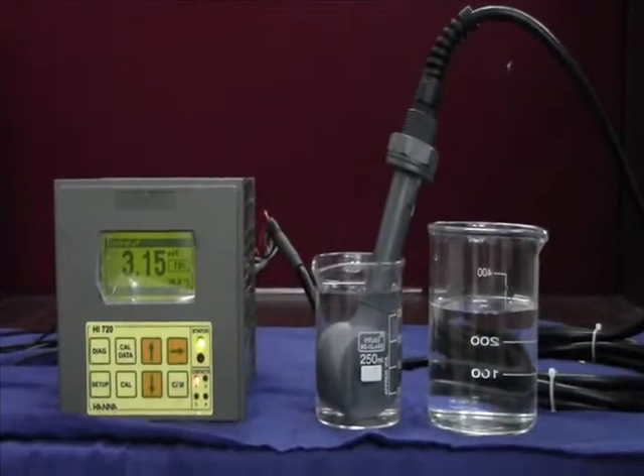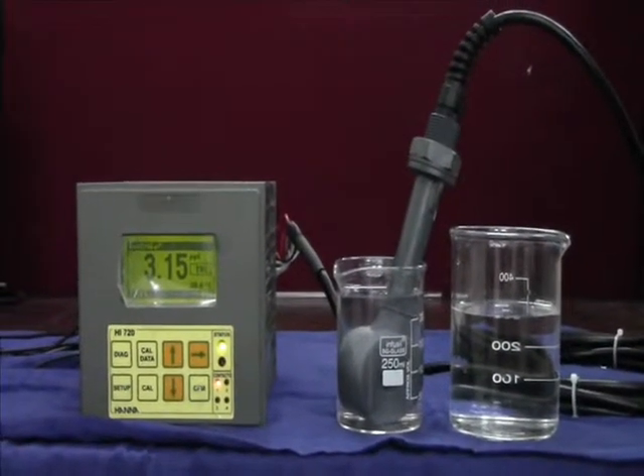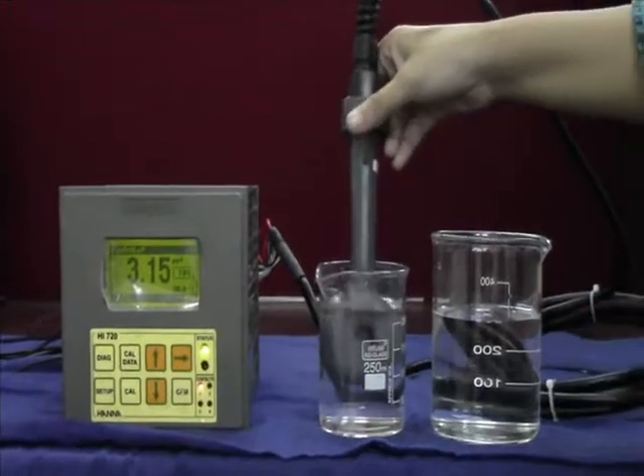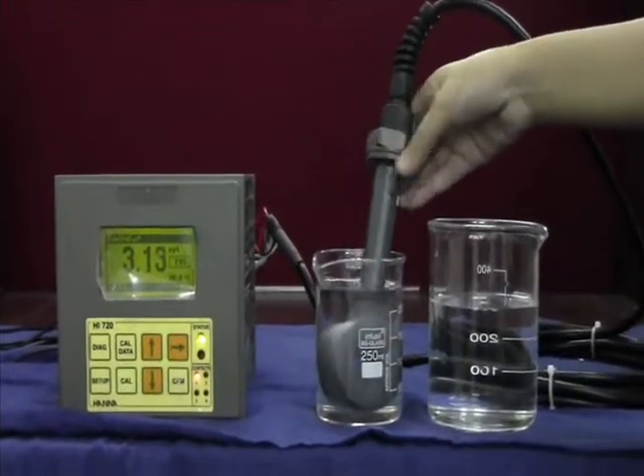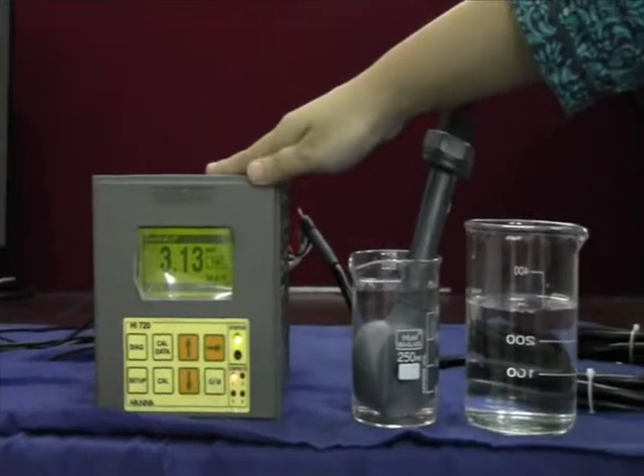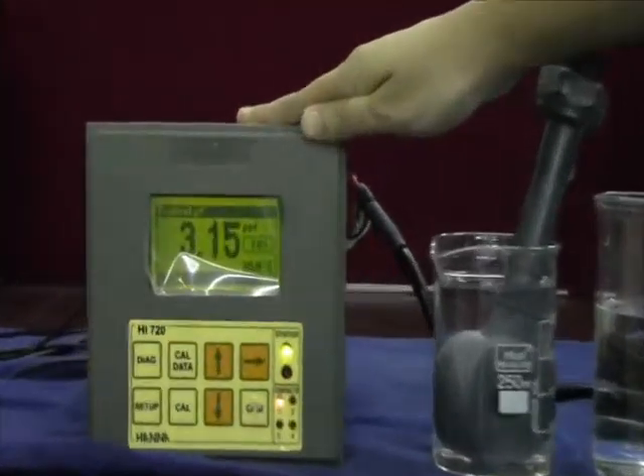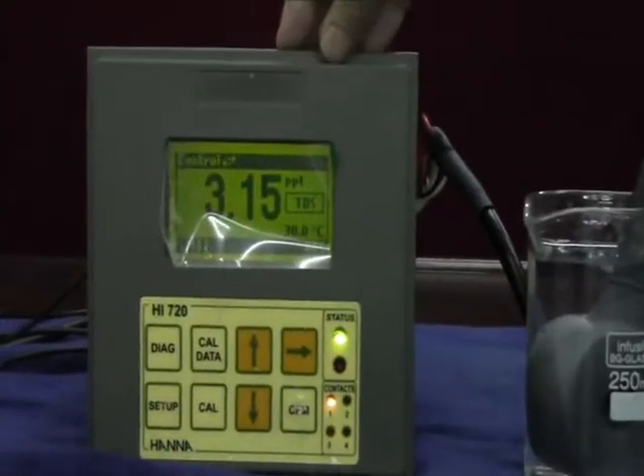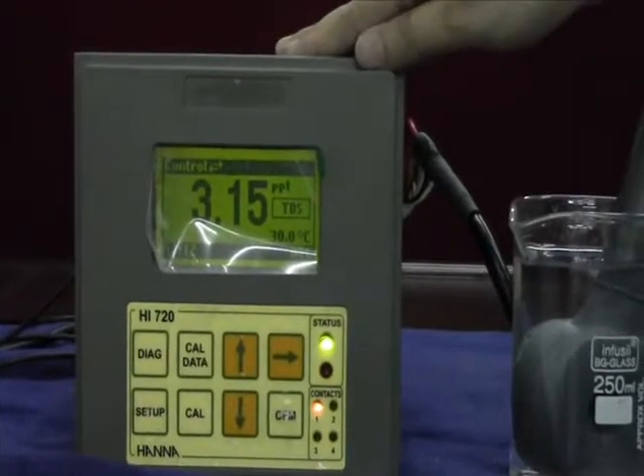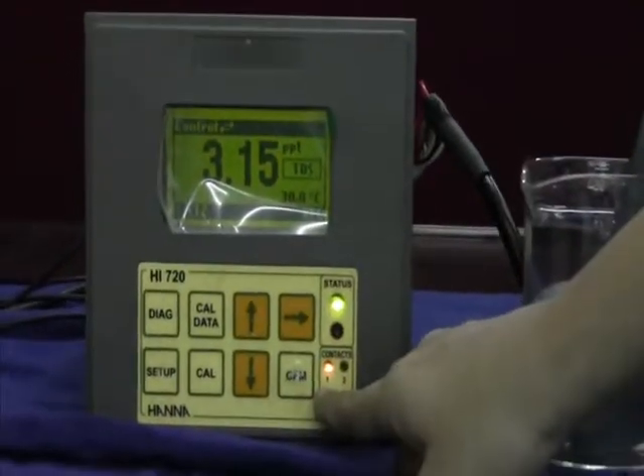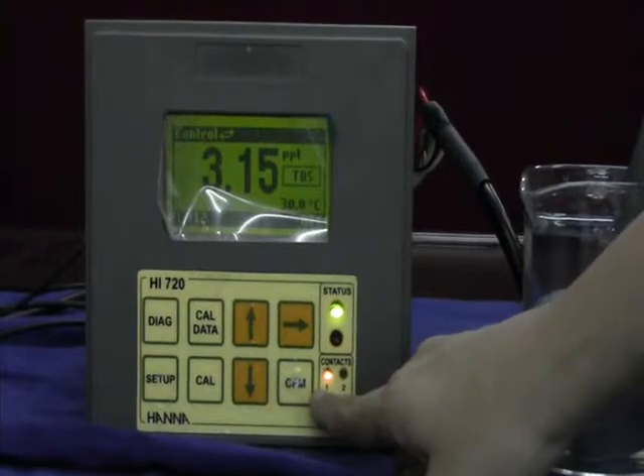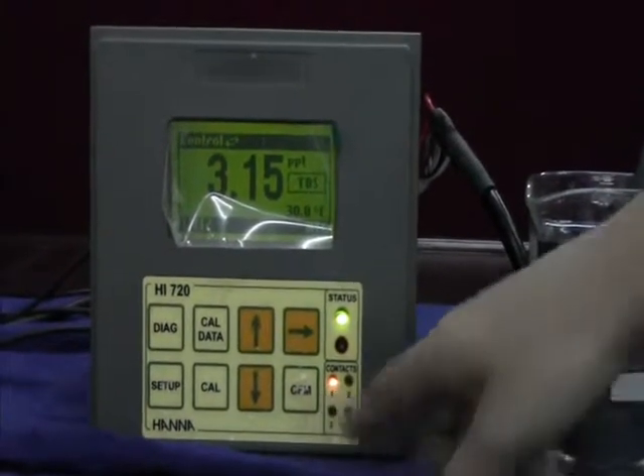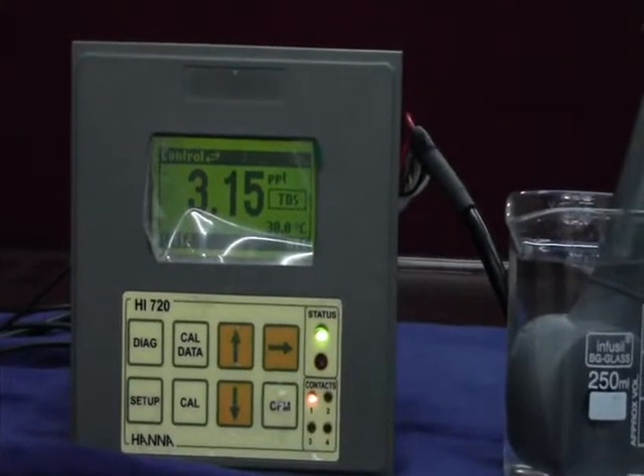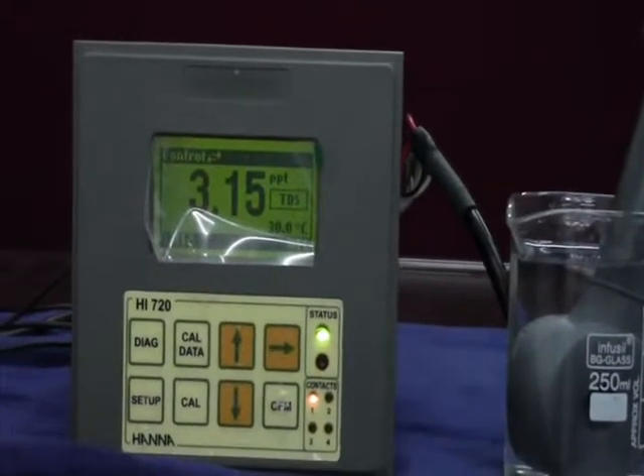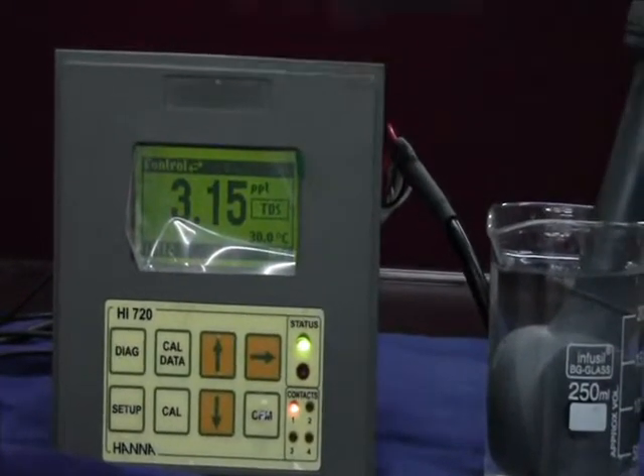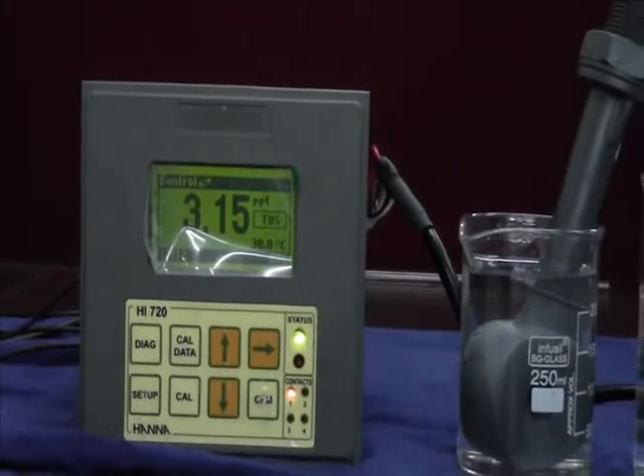Taking measurements with HI 720. The inductive probe is dipped in a sample. The controller reads the TDS in PPT. Currently it reads 3.15 PPT. The status of the LED is on, that is relay 1 is on. The device connected to the controller is running. For example, a pump which is controlled by the controller is on.